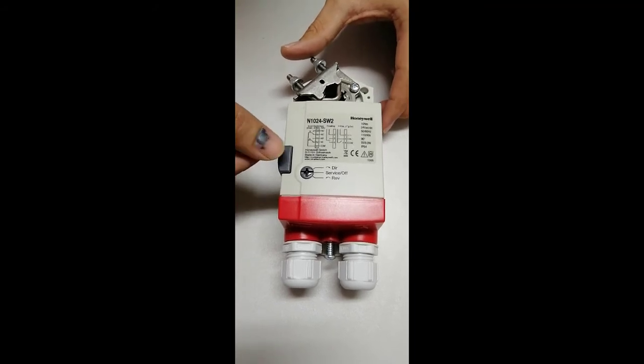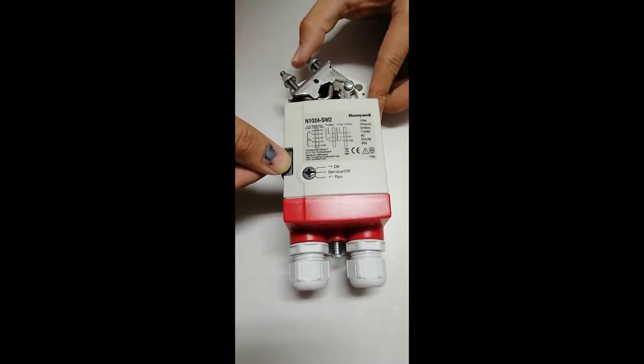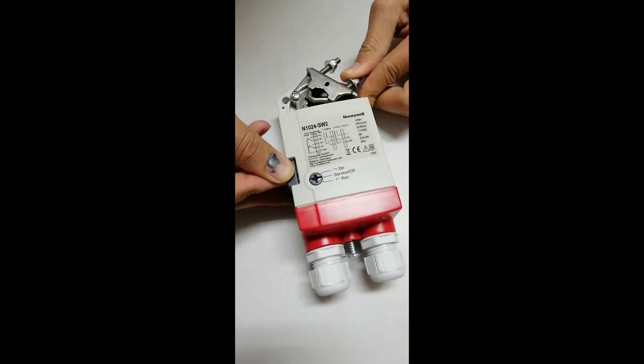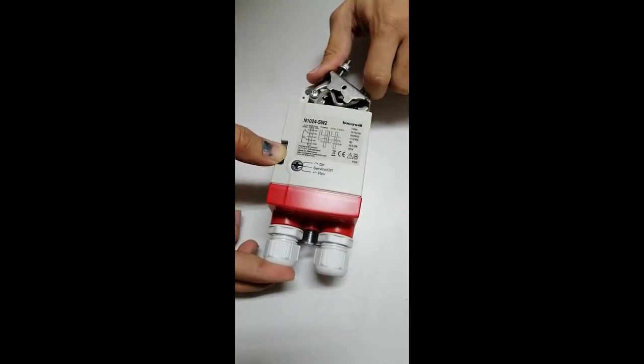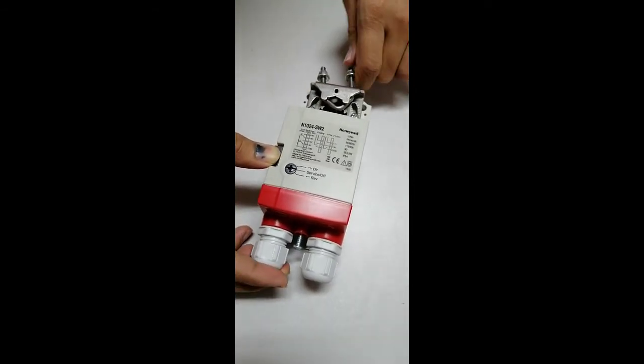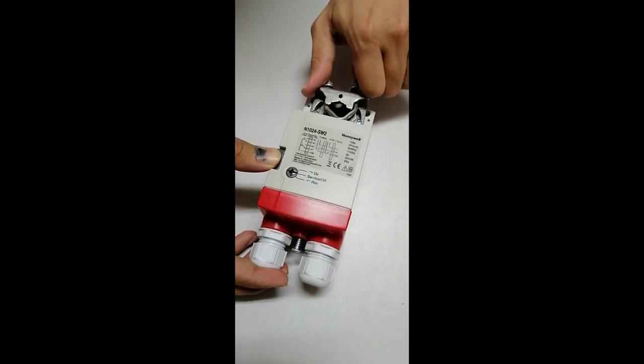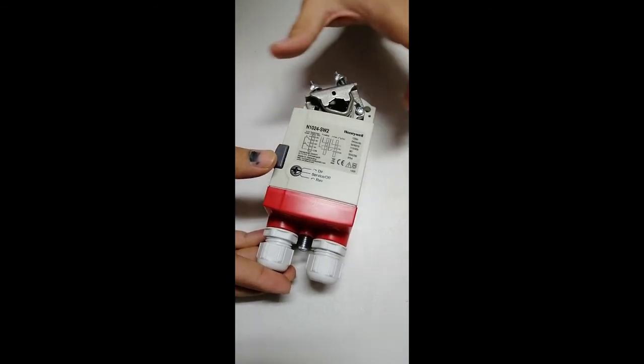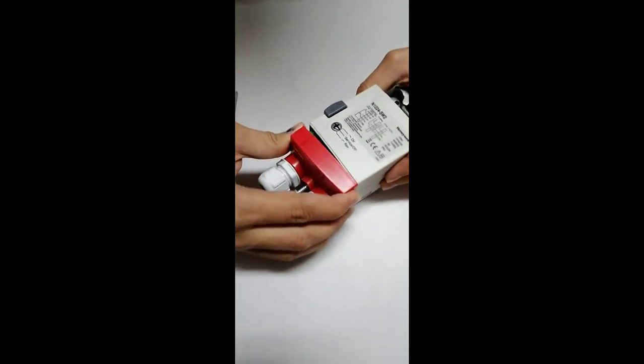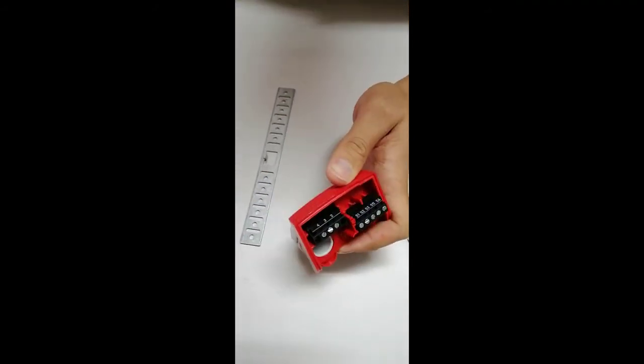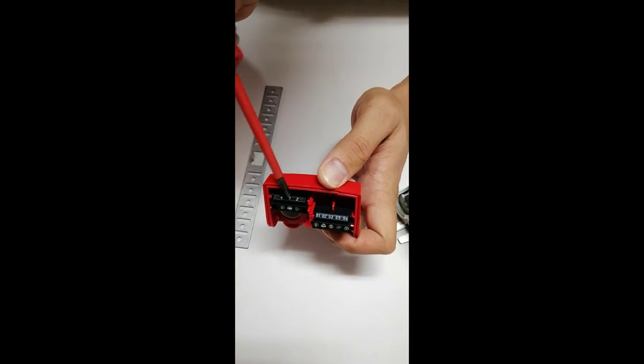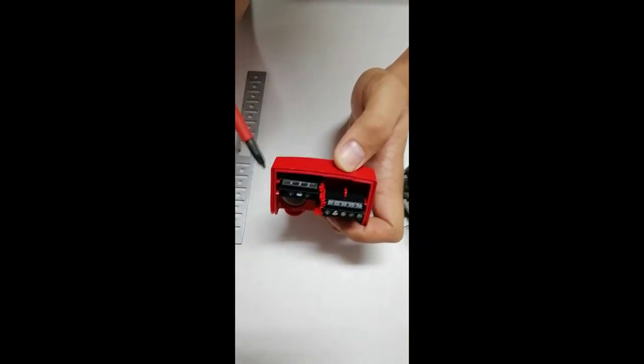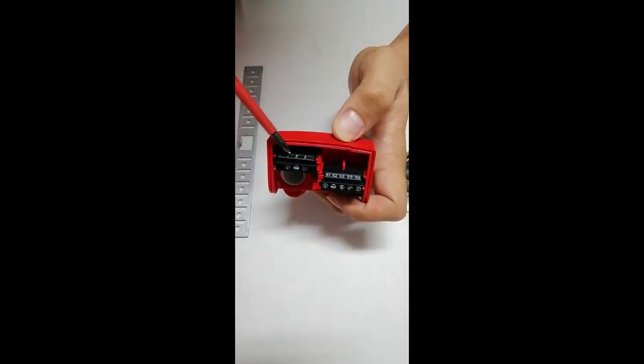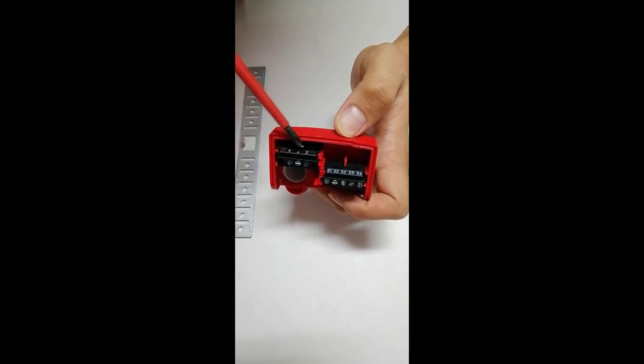Here we also have a clutch. By closing this clutch, we can manually rotate this actuator, like this, you can see. If you don't have a power supply or this damper has some problem, you can move the damper manually. Here is the connections part. These are the number 2, 3, and 4 points which we discussed earlier. We need a three core cable for the control.